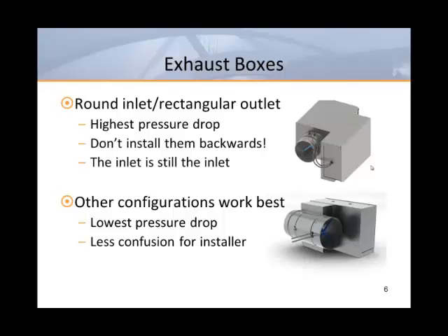Unfortunately, there's a lot of confusion about exhaust boxes. Many engineers mistakenly select the same type of box that they would use for a supply. The round inlet with rectangular outlet configuration that provides static pressure regain in the supply mode works against the exhaust fan and therefore increases the pressure requirements. Even worse, many installing contractors have mistakenly installed supply boxes backwards thinking that the box must be flipped to work as an exhaust. All of these problems can be avoided by either selecting a purpose-built exhaust box or using a retrofit air valve with a round inlet and a round outlet.